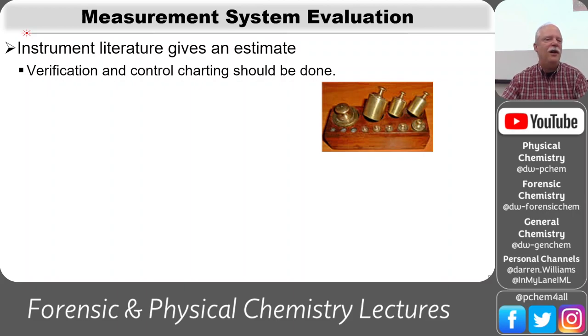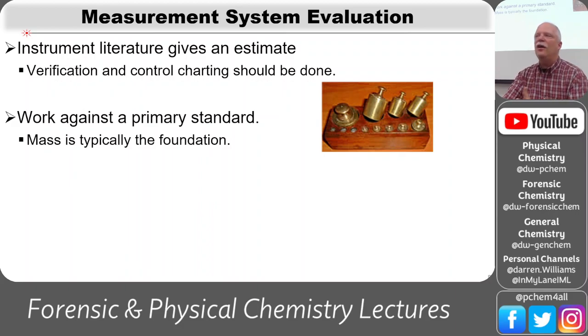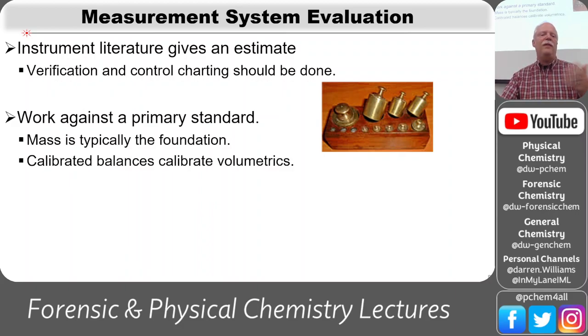You can verify that, or you can control chart it, especially for your balances. You can work easily against a primary standard in your balances, and mass is typically the foundation for all of these measurements. Because with your mass, then you can calibrate your volumetrics. You know the density of water at a given temperature, so you can fill your volumetrics up to a mark and weigh them. And you know that mark has got the exact amount of water in it that it should have at that given temperature.